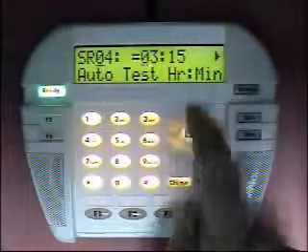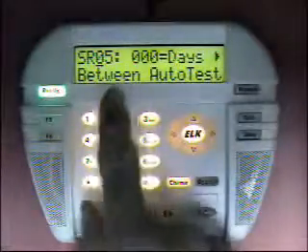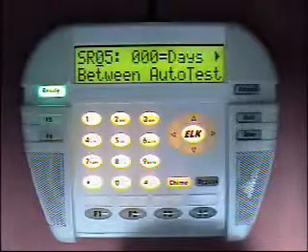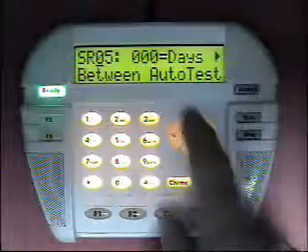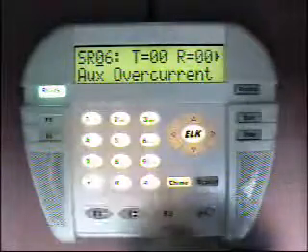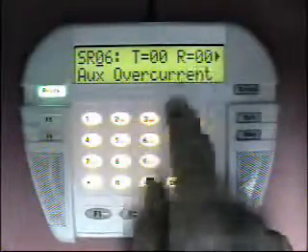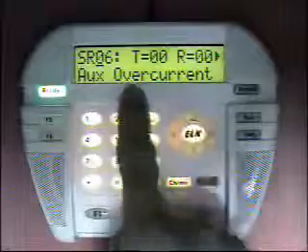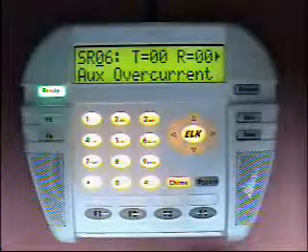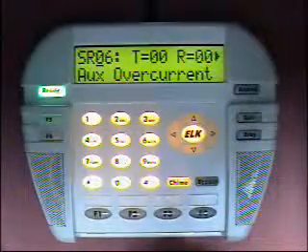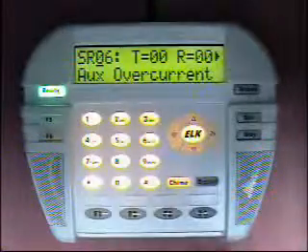The next option is the amount of time between automatic tests in days — up to 255 days between tests reported to the central station. The next option covers drawing too much current in the system: there is a trouble code and a restoral code sent to the central station. Be careful when sirens go off — with multiple speakers you can draw too much current and the system will report an over-current condition.